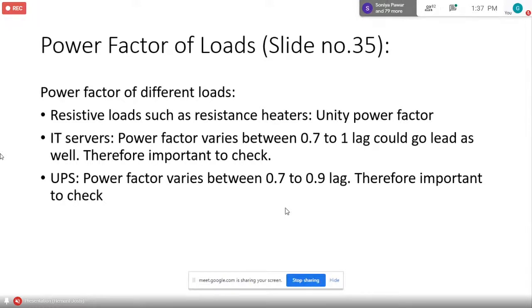There was a time until a few years ago when IT systems' power factor used to be poor, like 0.7 lag. Nowadays, IT servers have the opposite problem. They come at 0.98 lag or sometimes 0.98 lead. So IT systems are no more a problem generally, as far as power factor is concerned. UPS power factor varies between 0.7 to 0.9 lag, but this again depends on the IT equipment it is supplying. So nowadays this is also not a problem.